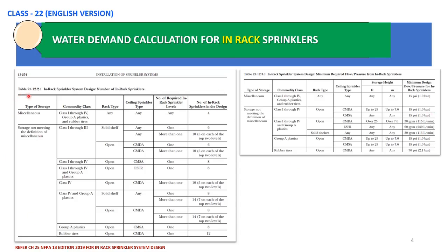From Table 25.12.2.1 we can identify the number of in-rack sprinklers to be considered in our design to calculate the water demand. From Table 25.12.5.1 we can determine the minimum design flow and pressure for in-rack sprinklers. I will explain in detail.